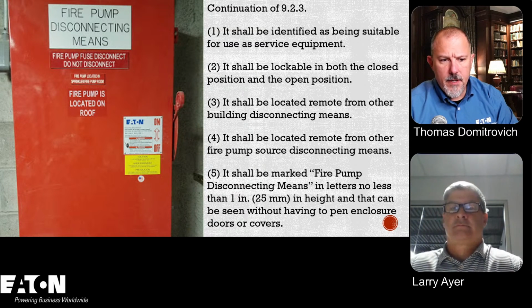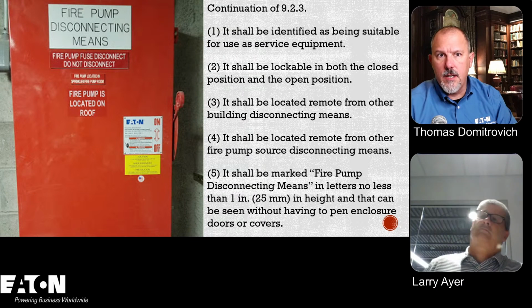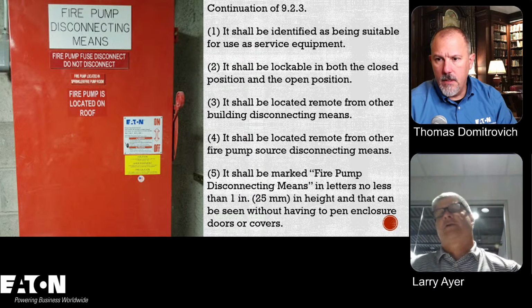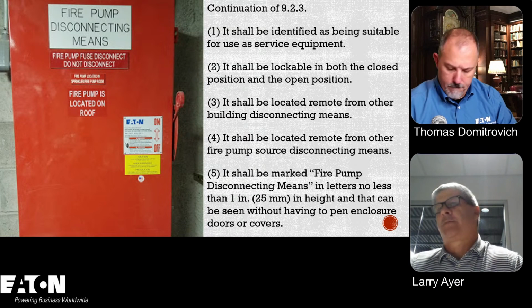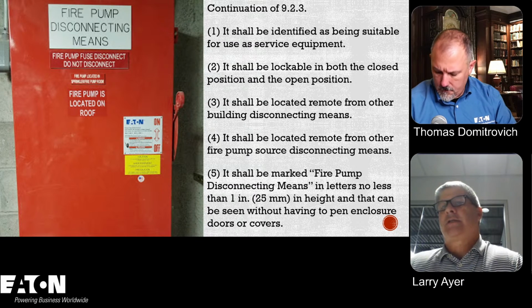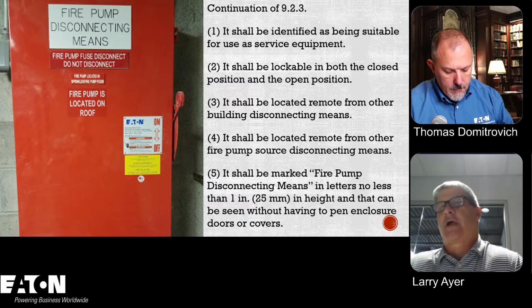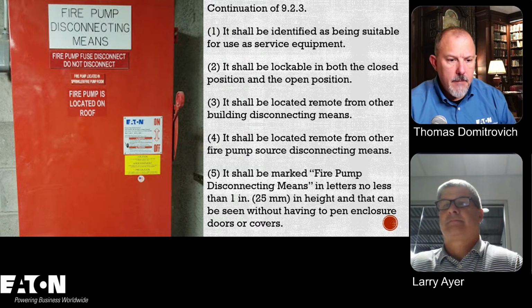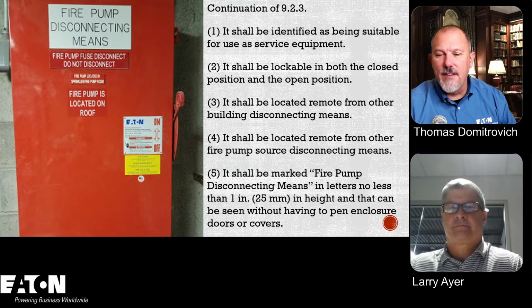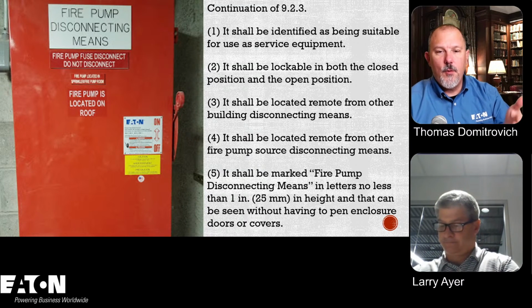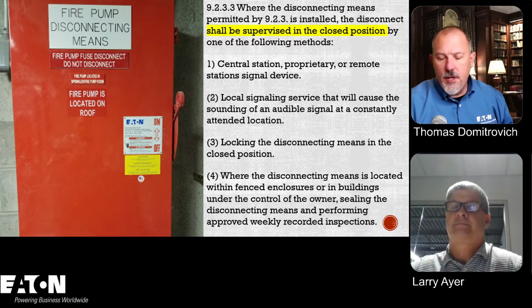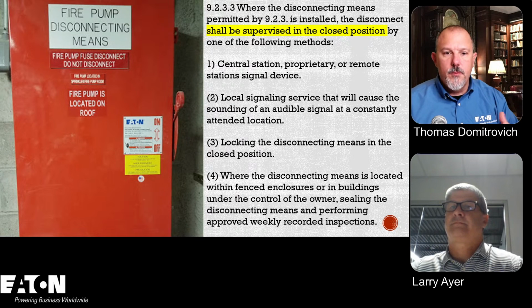Yep. Now, Felix asks, is overload protection forbidden? Like your thermomagnetic, I guess, on the motor. I mean, we have protection of the motor. There's overcurrent protection, but we're not worried about locked rotor and whatnot, right? Right. You cannot put overload protection in these circuits because you don't want it to trip. Right. And so if you end up with the locked rotor condition, that's why you size a lot of these circuits above the locked rotor current, to make sure you're adequate, that you don't have nuisance tripping. Yep. And then the commenter is asking about selectively coordinating one level of overcurrent protective device, and he's right that you would only have to do that in your feeders when you have multiple overcurrent devices.